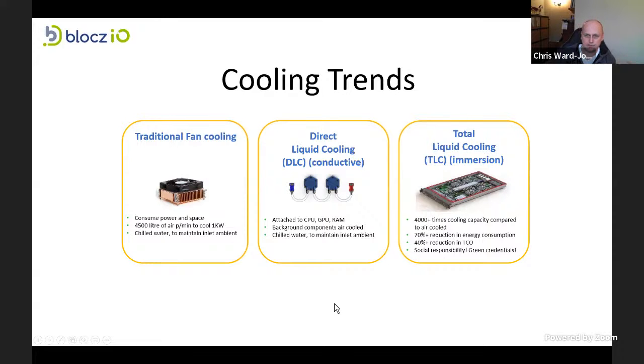At the opposite end of the scale, we have what we call total liquid cooling, or immersion cooling. It sounds counterintuitive, but what we do is take all of the IT and submerge it in a liquid. The first thing you'd think is it would go pop, because electricity and water don't mix. But it's not water, it's a dielectric fluid that doesn't conduct electricity. Anyone who's accidentally taken a breath underwater while swimming knows water is a lot denser than air, and because of that density, it's an awful lot more effective at conducting and moving heat. It's in the order of about 4,000 times more effective at carrying heat away from electrical components.